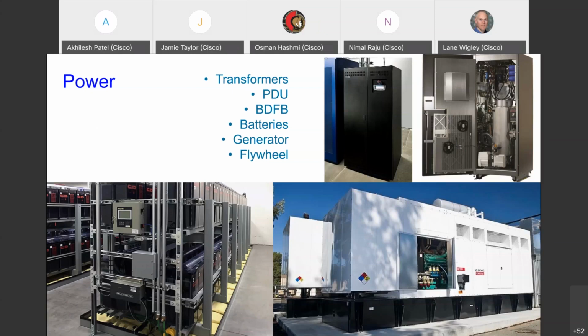Traditionally, telcos will have batteries, running 48 volt DC to their equipment, running DC through these batteries - that's on the bottom left here. If the power into the building fails, they start powering things off of these batteries, and while that's happening, the generators, on the bottom right, power up. Those generators usually have enough fuel for maybe a day or two to keep generating power.